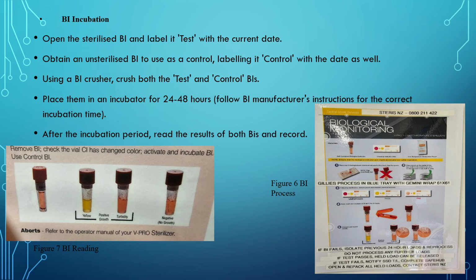BI incubation. Open the sterilized BI and label it test with the current date. Obtain an unsterile BI to use as a control, labeling it as control with the date as well. Using the BI crusher, crush both the test and control BIs. Place them in the incubator for 24 to 48 hours according to the manufacturer's instructions for the correct incubation time.